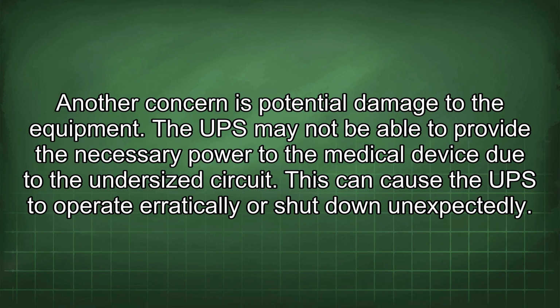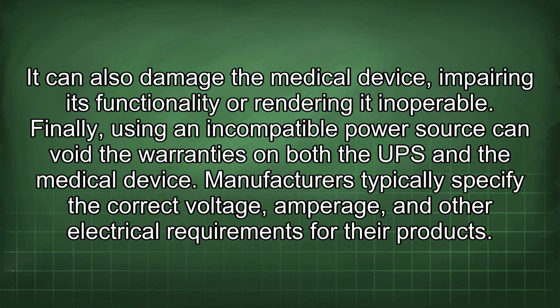The UPS may not be able to provide the necessary power to the medical device due to the undersized circuit. This can cause the UPS to operate erratically or shut down unexpectedly. It can also damage the medical device, impairing its functionality or rendering it inoperable. Finally, using an incompatible power source can void the warranties on both the UPS and the medical device.